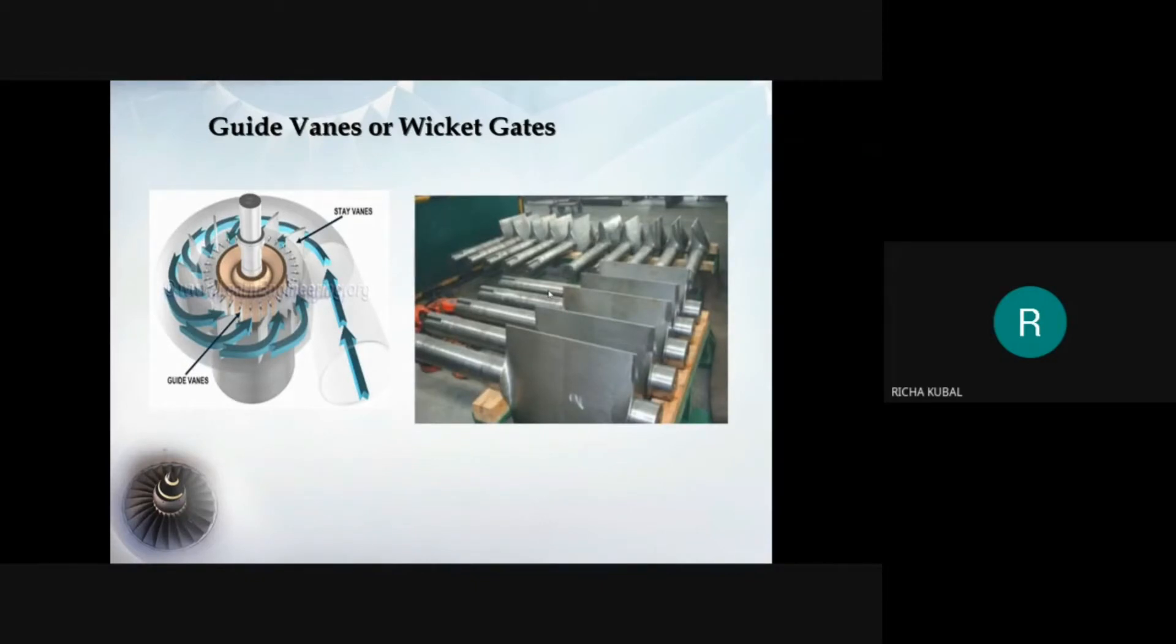Guide vanes also regulate the discharge according to the load acting on the turbine. It can be done by swinging the guide vanes about their own pivot by opening or closing the guide vanes passage. Swinging action of guide vanes are obtained by regulating rod connected to regulating shaft and is operated by servo motor governing mechanism. Materials used to manufacture wicket gates are structural steel and stainless steel.